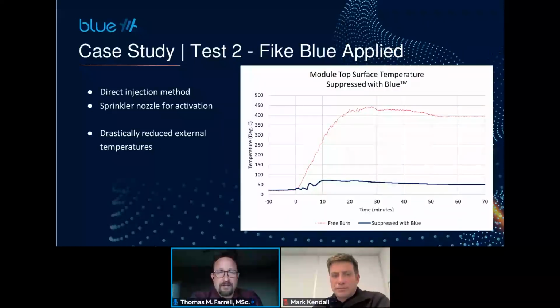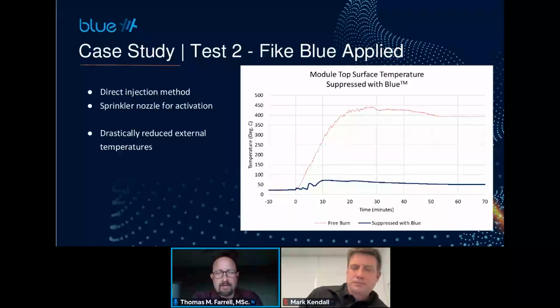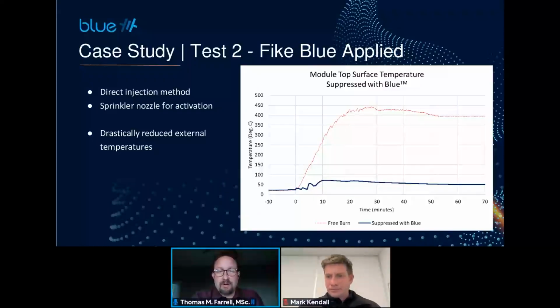knocked down those temperatures. You can see in this particular example, the high temperature never even reached 100 degrees Celsius. UL 9540A calls out 97 degrees above ambient temperature when you start as kind of a litmus test. If you get to that temperature, it's likely that you can cause thermal runaway in a neighboring module. You can see in this particular case, it didn't even get to that level, which is a really good thing.